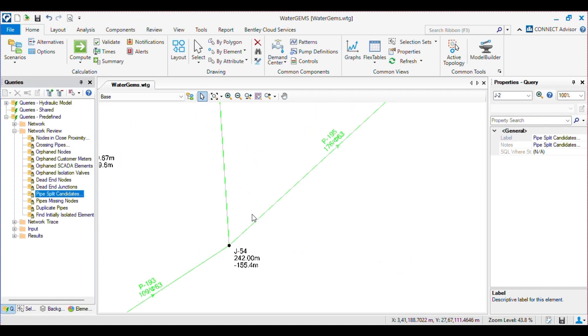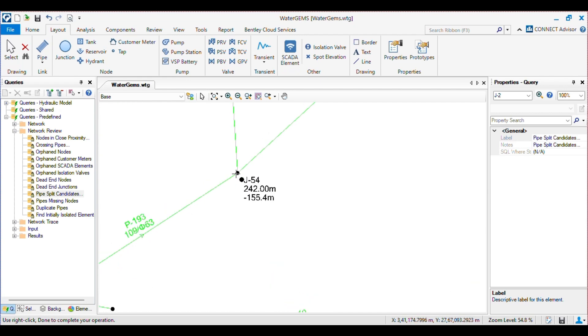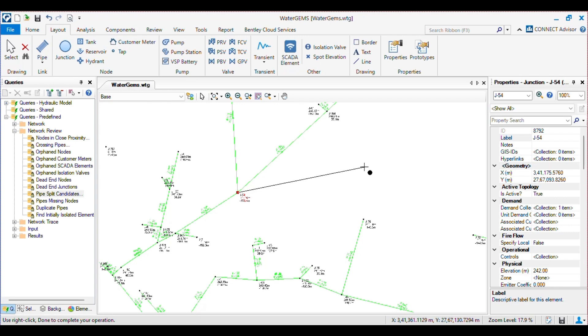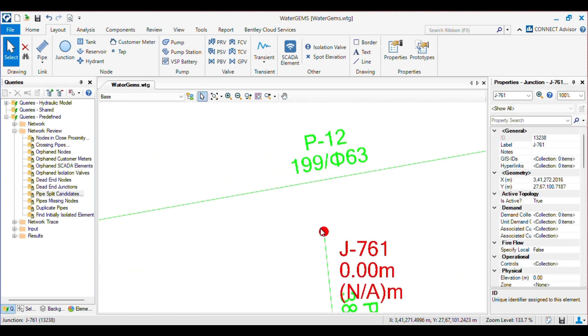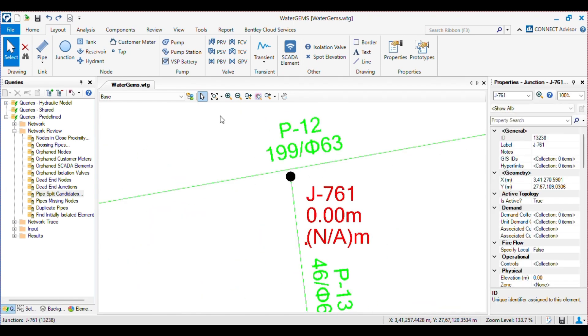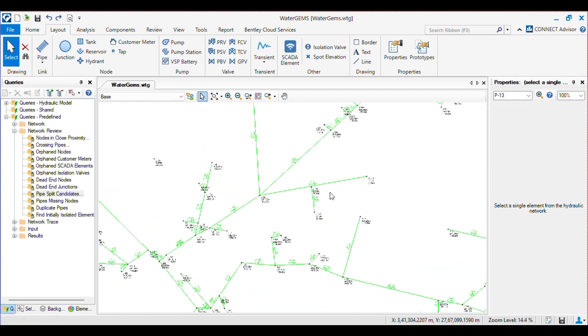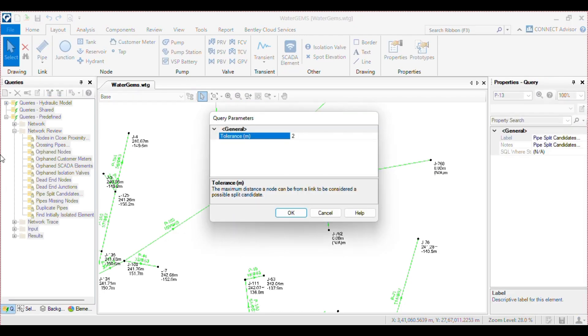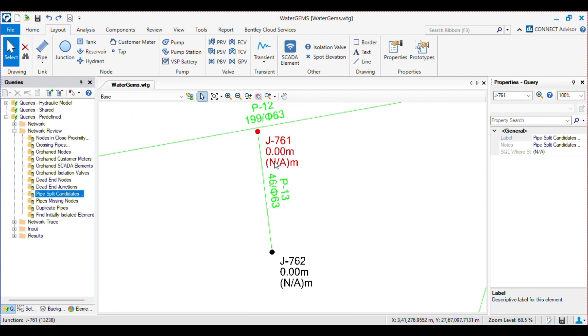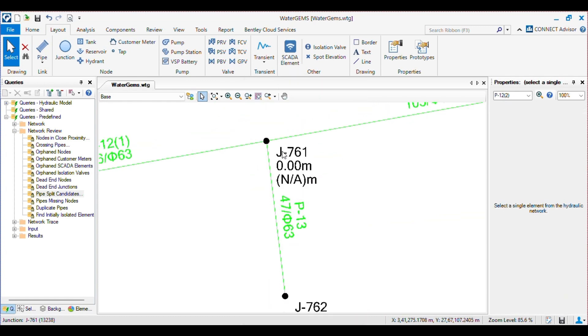Then we have Pipe Split Candidate. If you set a tolerance of 2, it will show you any pipe split candidates — meaning if you have a pipe that is not connected to a junction, or a junction not connected to the pipe. This commonly happens when you generate a model. By using this Pipe Split Candidate query, you can identify all the missing nodes or missing pipe connections. Clicking on that, you will see the junction is highlighted, and then you can move and connect it to the pipe.